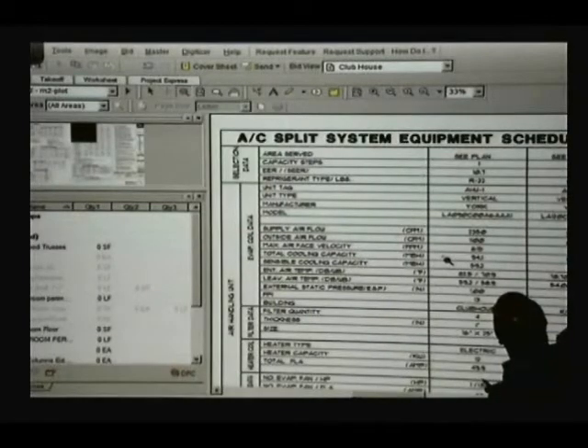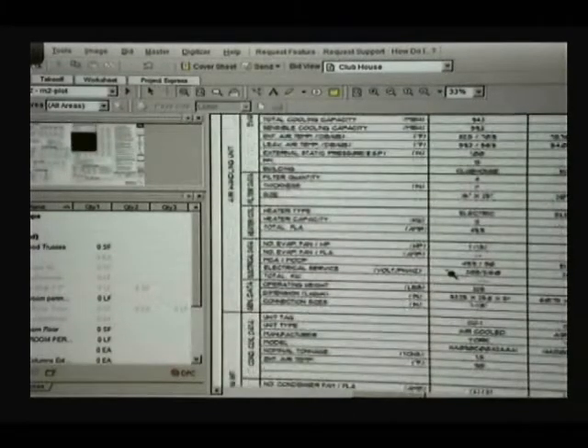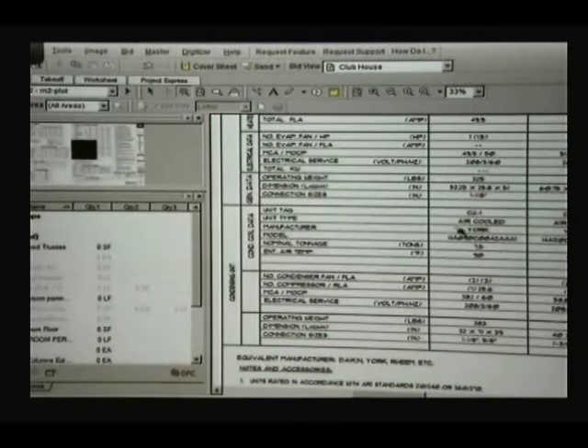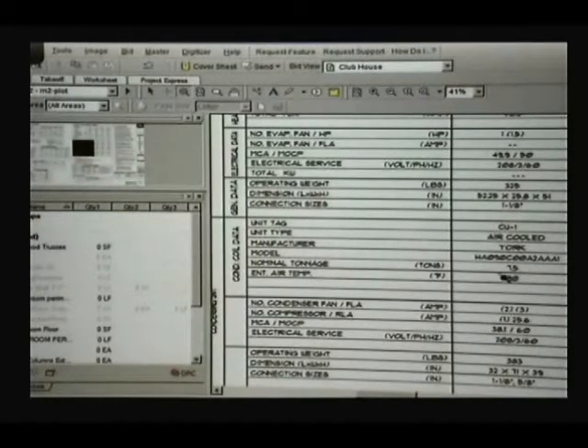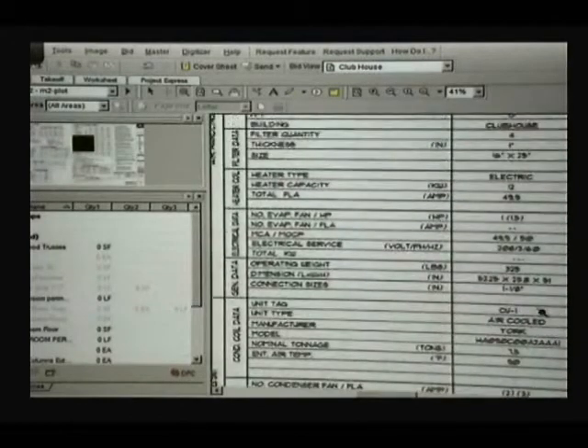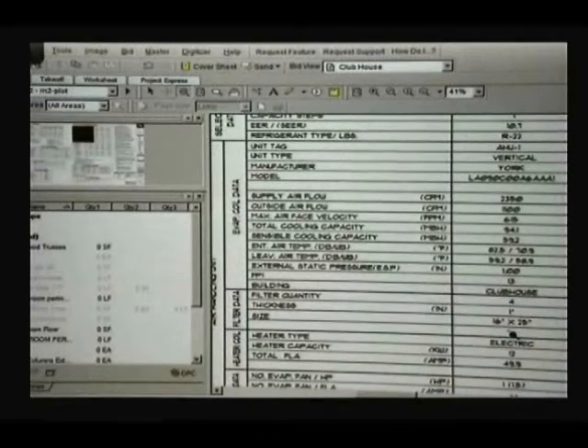Under the cooling data, it shows 1 R-22, 10.7 — and it says cooling tons. So it's a 7.5-ton unit. That's how refrigeration is measured — in tons of refrigeration — and that is the number you want to use to estimate the cost of this unit.